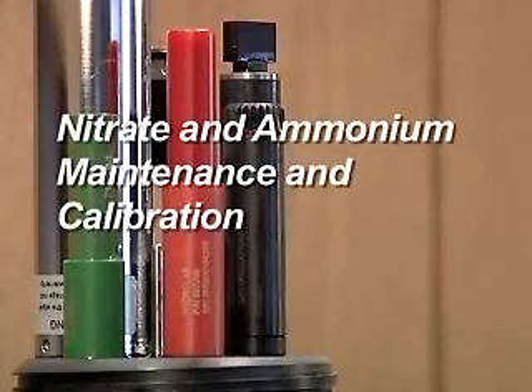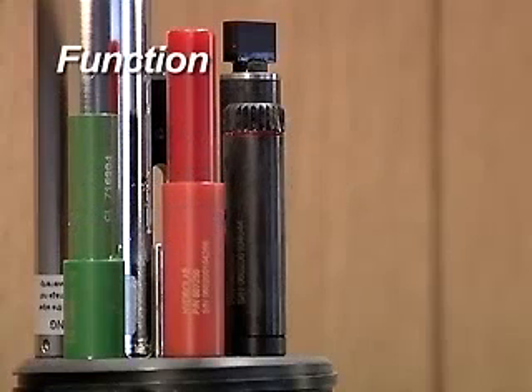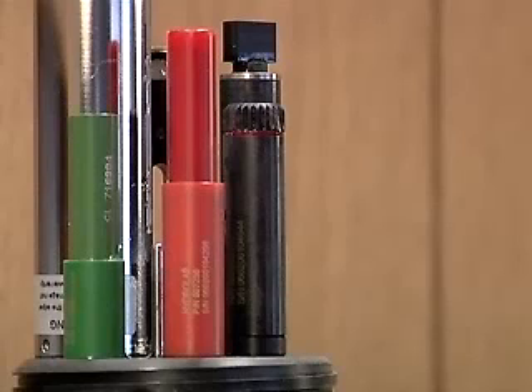Nitrate and ammonium maintenance and calibration. Function. The ammonium and nitrate ion sensors use two electrodes to measure the electrical potential between a known ion concentration and the sample. The electrode inside the sensor tip is surrounded by a solution of a known concentration of the appropriate ion. The other electrode is the reference electrode used by the pH sensor.